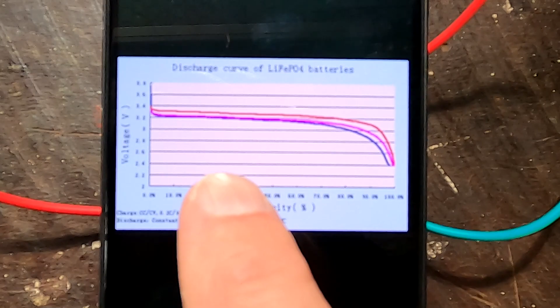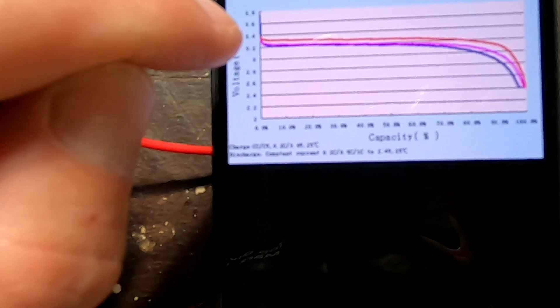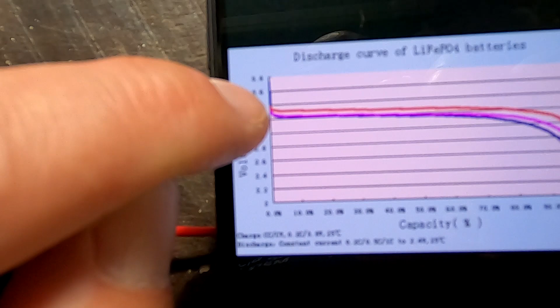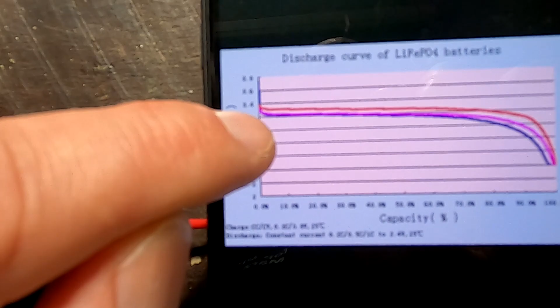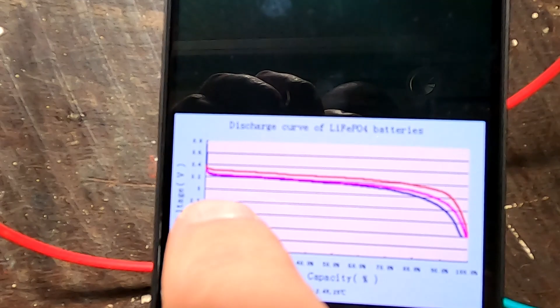If you have a look at the discharge curve of such a lithium-ion battery, you can see the 3.4 volts will only be achieved at the very beginning when the battery is fully charged, and as soon as you put load on it, if you take 1% of the battery, you're already down to 3.3 volts. And 3.2 volts is the nominal voltage of these cells.